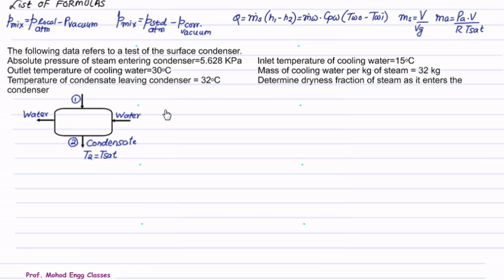The following data refers to a test of a surface condenser. The absolute pressure of steam entering the condenser is 5.628 kPa (P mix). Inlet temperature of cooling water TWI is 15°C, outlet temperature TWO is 30°C. Mass of cooling water per kg of steam, MW/MS, is 32. Temperature of condensate is 32°C.